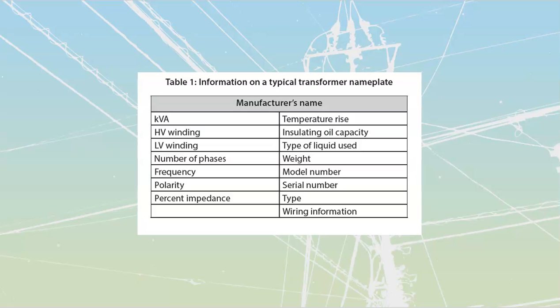Let's talk about what's going to be inside of here, just on a basis by basis. The first thing that they're going to have is the kVA rating. Transformers are always rated in kVA. We never say them in kilowatts, because then what do we do when we've got an inductive load, right? We've got a lot of inductive loads out there. So instead they say, look, we're going to put it in as kVA. How good of a power factor you're passing through is all the way up to you as the electrician.